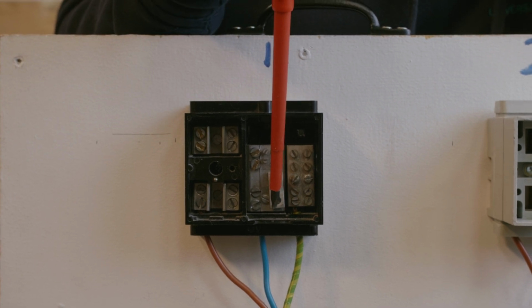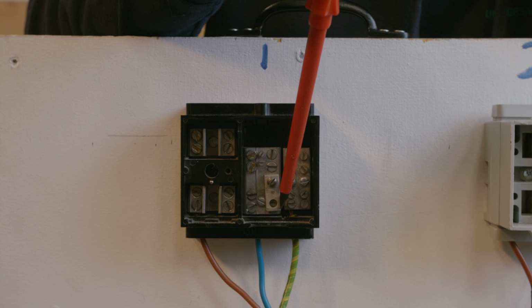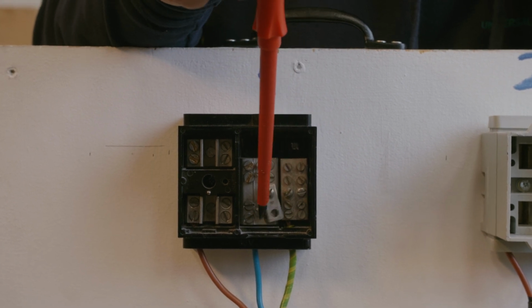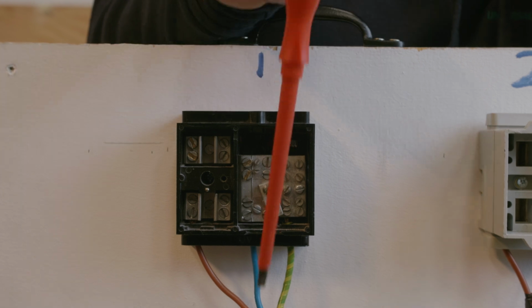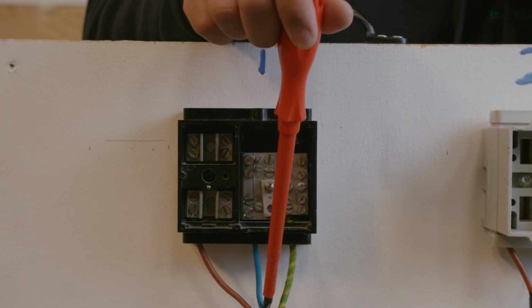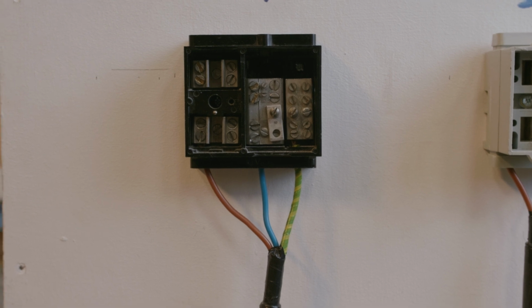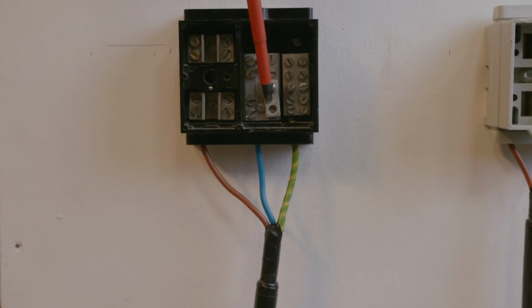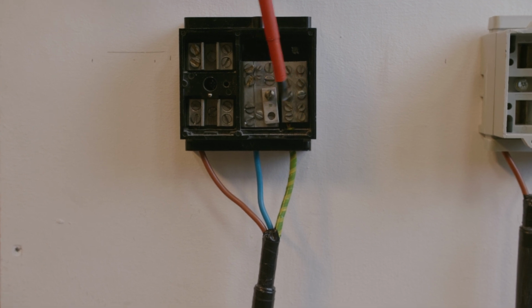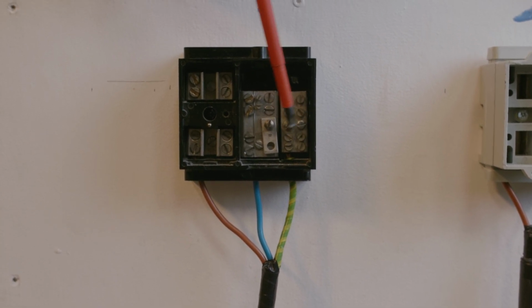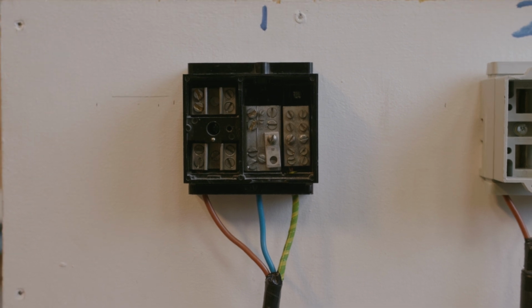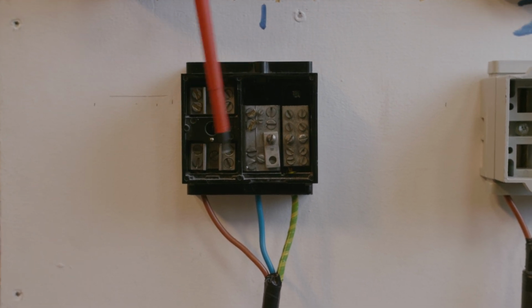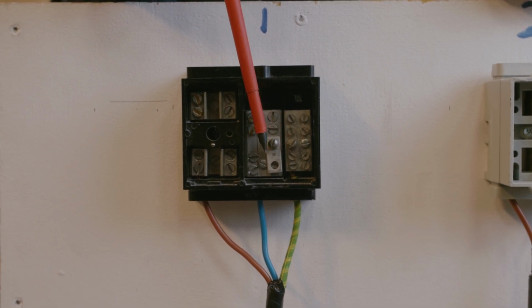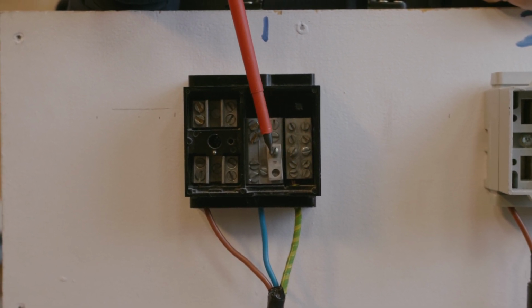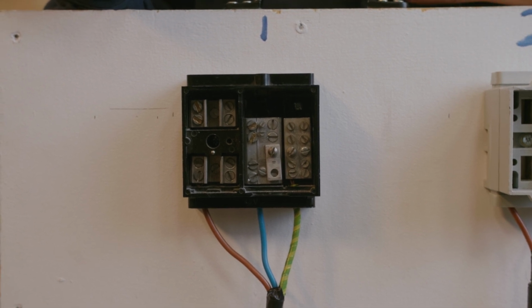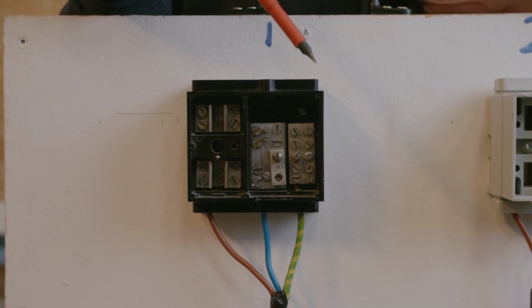But the main reason I wanted to show you this one is because with these type cutouts, you can actually see there is a bar inside, okay? So that bar there, which you can see moving. If you look at the bottom, we've still got the line conductor, the neutral conductor and the earth, all coming in separately. Whilst that bar is not attached across, like so, you have got earth, neutral and line all completely separate, okay? So obviously the line should always be separate by itself, but the main one that we're looking at here is the neutral and earth. While those two are separate, that is classed as a TNS system because neutral and earth are completely separate.